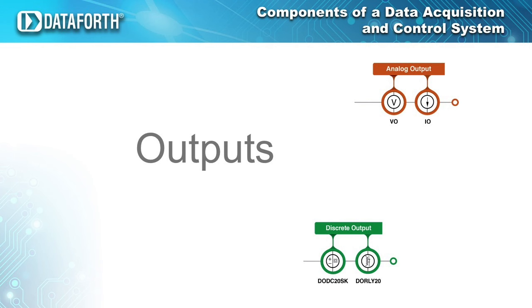Besides input modules, many of the existing data acquisition systems also offer output channels to support control functions and feedback loops. Those outputs are generally analog process voltages and process currents. Special cases do require digital outputs, such as discrete output channels that can switch DC signals and sink currents, or relay output channels that can switch currents and voltages. Those special function output modules come in handy when special requirements call for a cross-point matrix switch or differential multiplexing for precision measurements, or in cases where multiplexer control is needed to allow combinations of switches to be closed or opened.